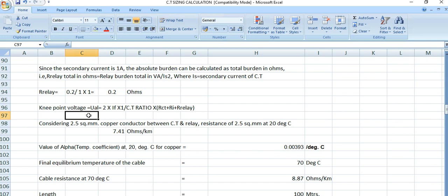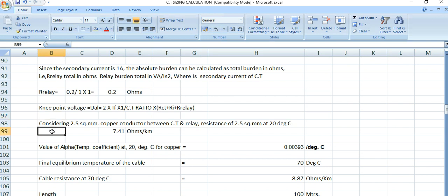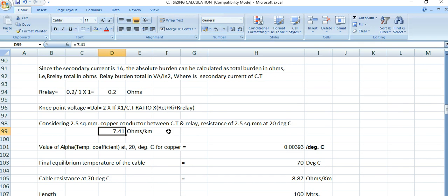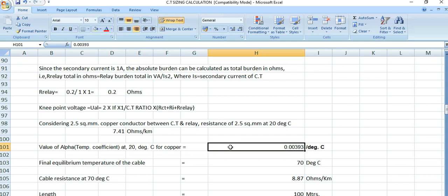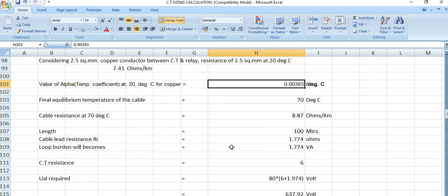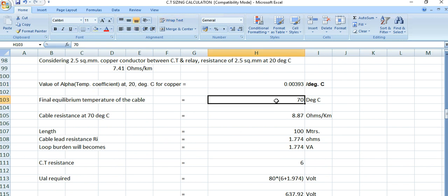We need to calculate the knee point voltage because beyond this knee point voltage the protection CT will get saturated. To avoid CT saturation we need to specify the knee point voltage for this PS class differential current transformer. We will consider 2.5 square mm copper cable between the PS class CT and the relay. The resistance of 2.5 sq mm copper conductor at 20°C is 7.41 ohms per km — you can get this from any manufacturer cable catalog. The alpha temperature coefficient at 20°C for copper conductor is 0.00393 per degree centigrade, and the final temperature for this copper conductor is 70°C.